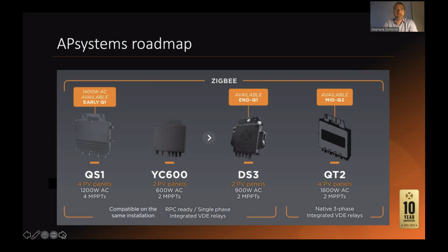And in the commercial arena, 3-phase, we are going to launch the QT2. It's also a quad - Q for quad, T for 3-phase, and 2 for 2nd generation. 1800 watt AC, 2 MPPT, which is not so critical for commercial installation, and it's the only microinverter worldwide which is native 3-phase. All these micros have the integrated VDE relay and will be CEC listed and approved.